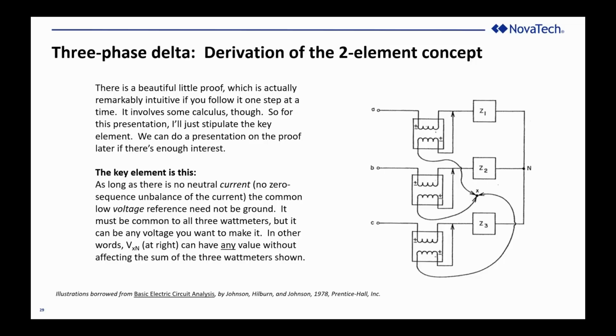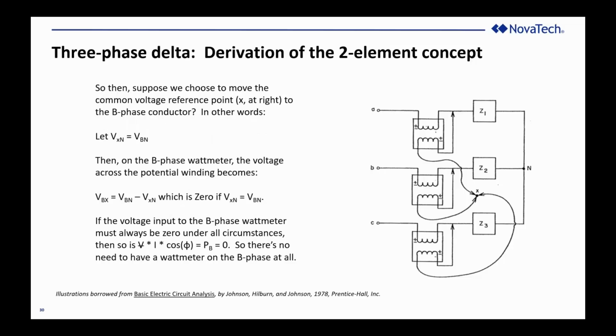Now, I'm not saying that that stands without proof. I'm on this slide specifically saying that requires proof before you can make that assumption, because it's not always true, and it's not intuitive that neutral current affects the common voltage point. I think that's the counterintuitive part. Why does the neutral current mean that I can move the voltage? Let's stipulate that that's a fact and prove it off the clock. So basically, once we've accepted that, there are a number of implications.